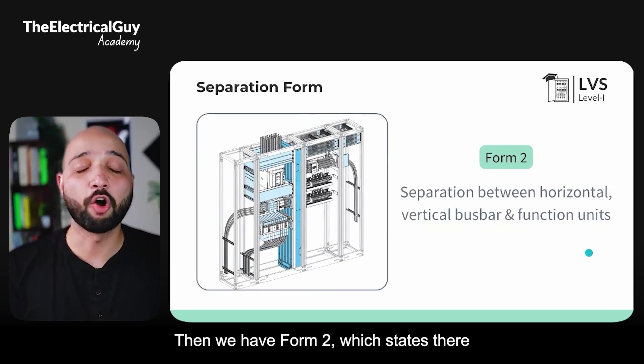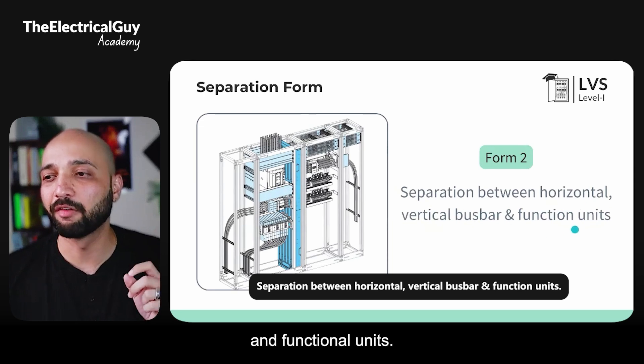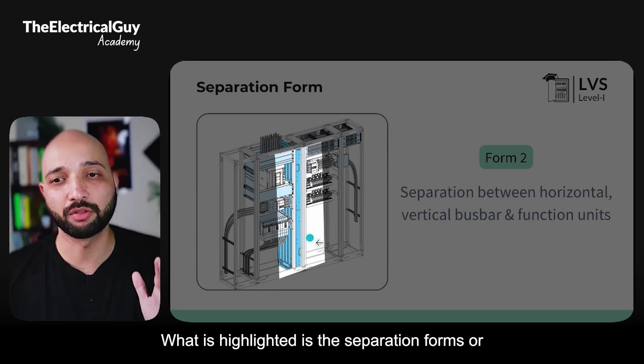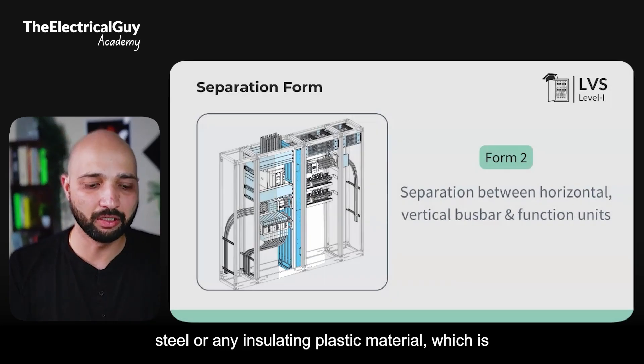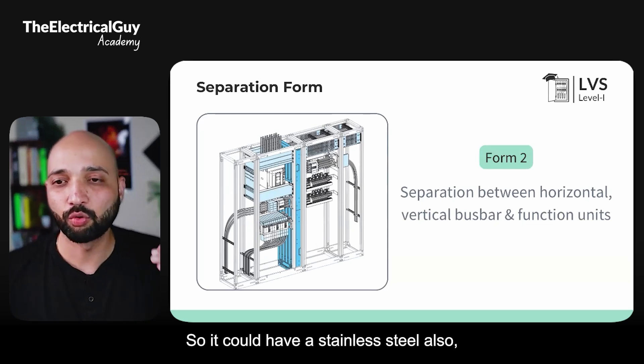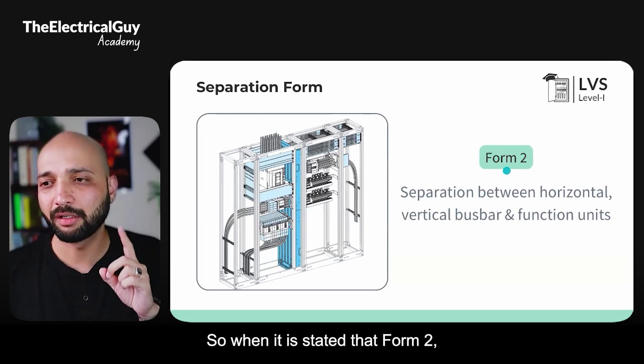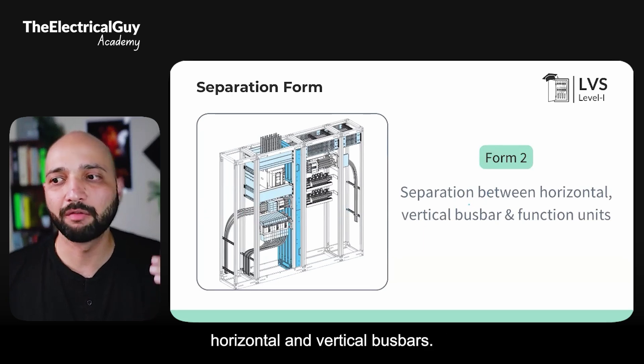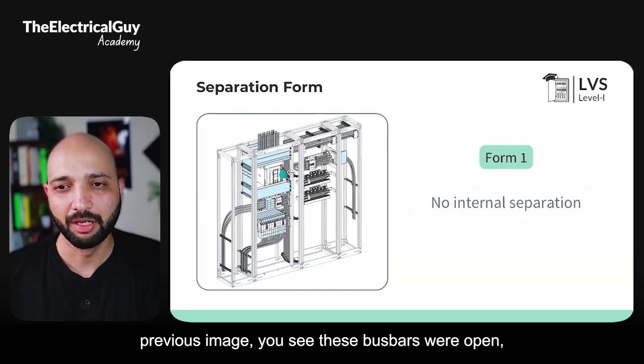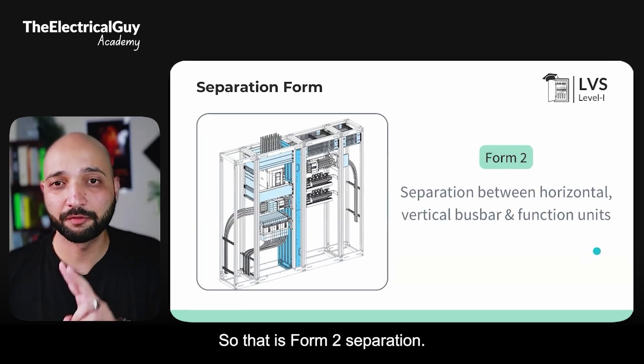Form 2 states there should be a separation between the horizontal and vertical busbars and functional units. The separator material could be sheet steel or insulating plastic material, depending on the type-tested design. You can see the busbars are now covered with the highlighted barriers — compared to Form 1 where the busbars were open, Form 2 covers them. That is Form 2 separation.